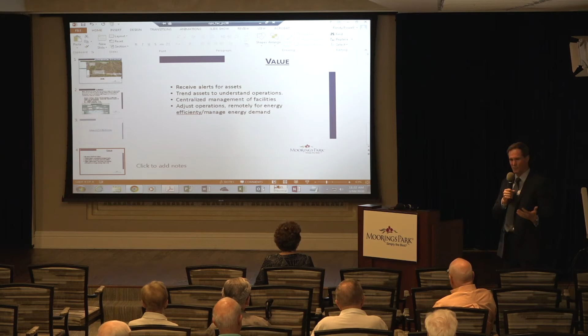Trending assets to understand operations. So in the Bauer Chapel, we had some issues where too much humidity was entering that building, and that's because we didn't have controls. We didn't understand that the outdoor air damper was open and bringing in way too much fresh air. You can look at those trends and understand how your building's operating, and drive efficiencies as well as avoid issues. Centralized management of facilities.